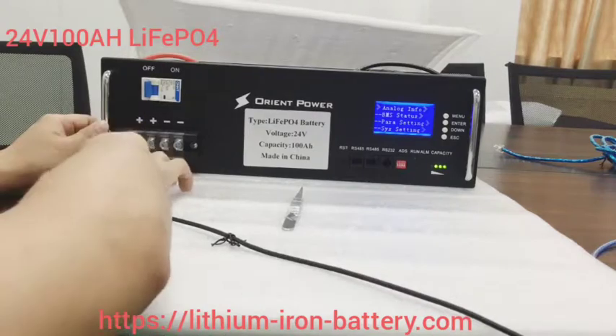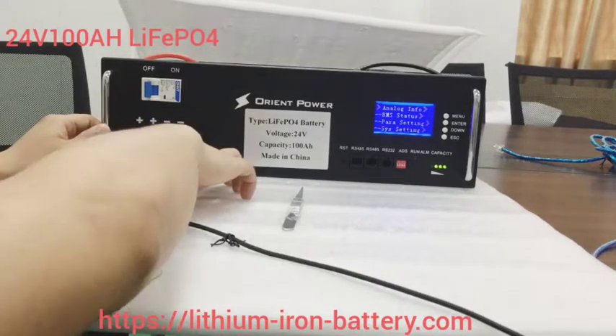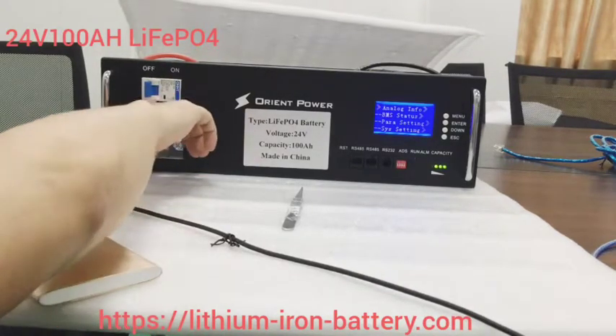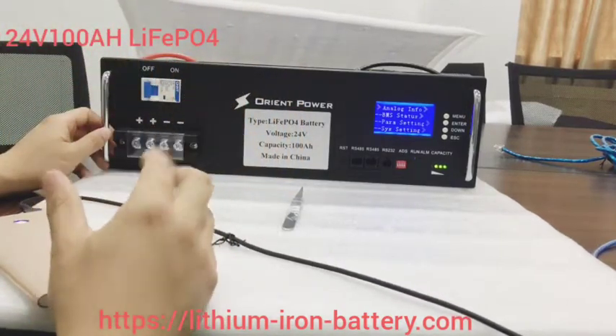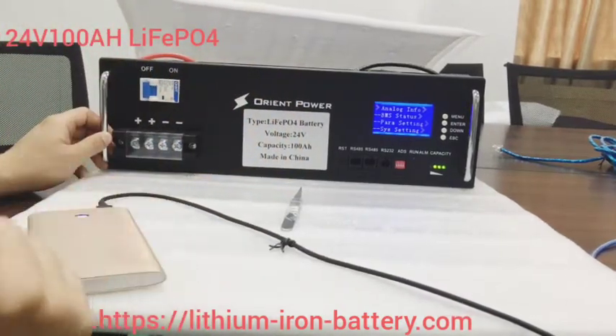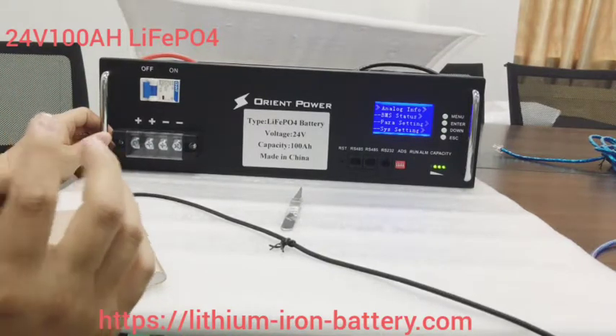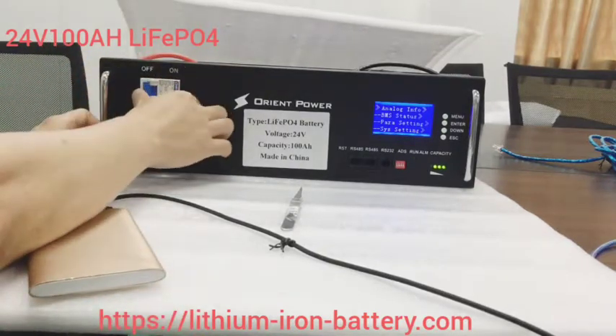Once you've done the connection, you can switch on, keeping the main breaker off. Keep in mind, keep the main breaker off, which is going to your inverter. Keep that main breaker off and switch on all these battery packs.